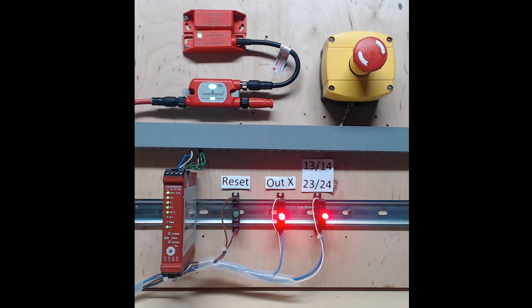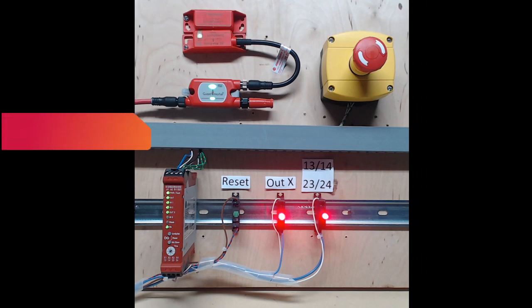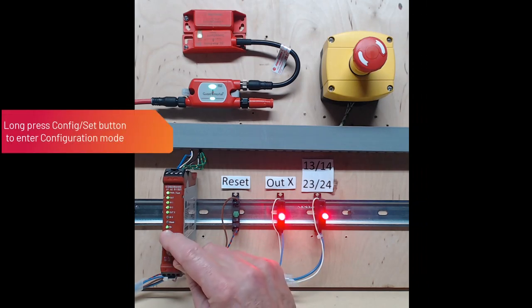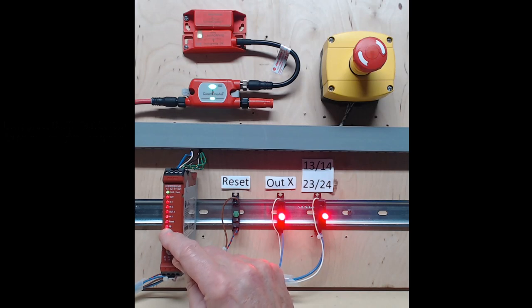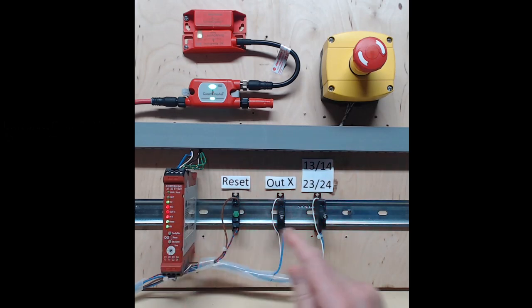To put the DG relay into configuration mode, I long press the config set button. After a short duration, the power LED will remain solid green, and all the other LEDs will flash red. Release the config button, and the DG goes into configuration mode. And notice also that the outputs turn off. While in configuration mode, the power indicator flashes green.